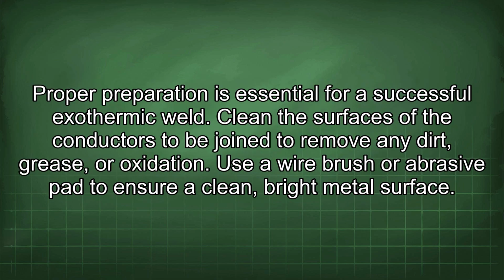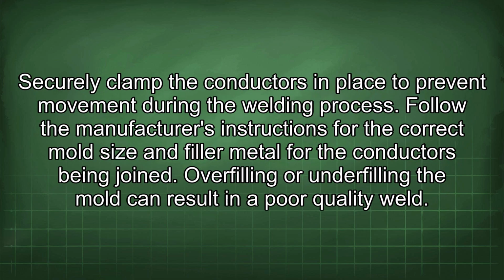Proper preparation is essential for a successful exothermic weld. Clean the surfaces of the conductors to be joined to remove any dirt, grease, or oxidation. Use a wire brush or abrasive pad to ensure a clean, bright metal surface. Securely clamp the conductors in place to prevent movement during the welding process. Follow the manufacturer's instructions for the correct mold size and filler metal for the conductors being joined. Overfilling or underfilling the mold can result in a poor quality weld.